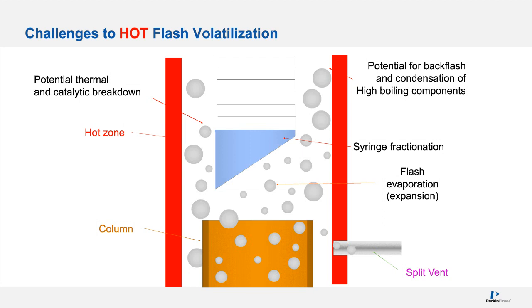There's potential for backflash and syringe fractionation. Syringe fractionation is when there's too much dwell time of the needle in the injector port. What happens is, if there's too much dwell time, we get discrimination favoring the low boiling point compounds, because these compounds start volatilizing out of the syringe. So what we want to do is inject as quickly as possible. If you're with your autosampler in the fast mode, this typically is avoided. Most of the concern is with backflash, and I'm going to get into that right away.